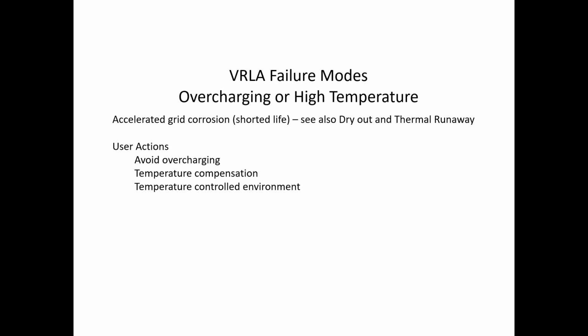Overcharging or a battery in a high temperature, all the manufacturers have a sliding scale. Some rectifiers have temperature compensation circuitry already incorporated into them, so that if your battery is going to be operating at 90 degrees F for certain parts of the summer, but yet is susceptible to lower temperatures in the winter, there's circuitry that'll actually lower that float voltage in the summer and then raise it in the winter. So that can also manually be done.